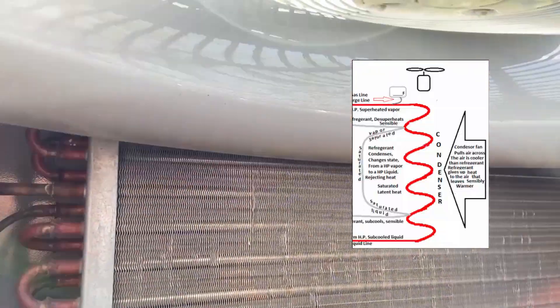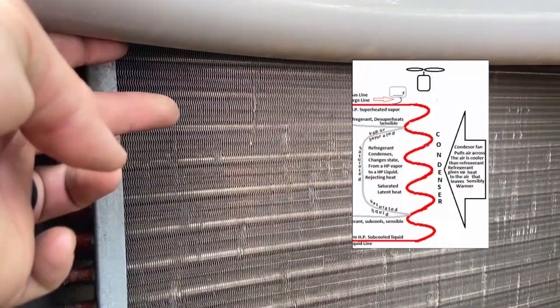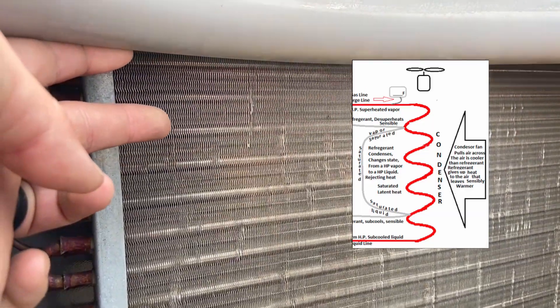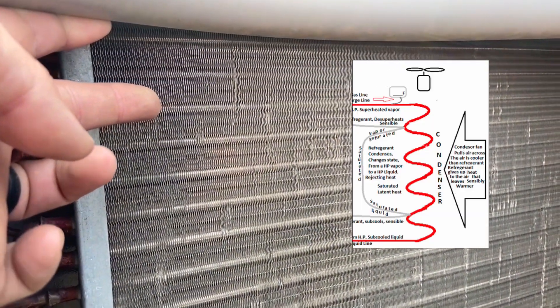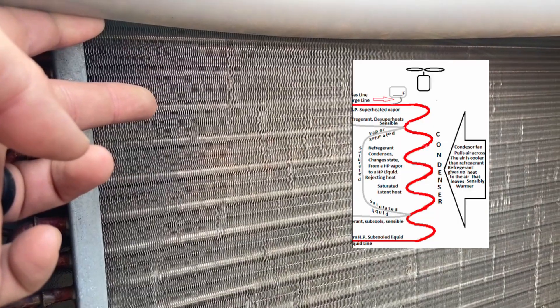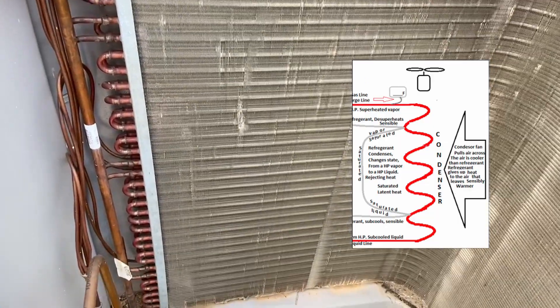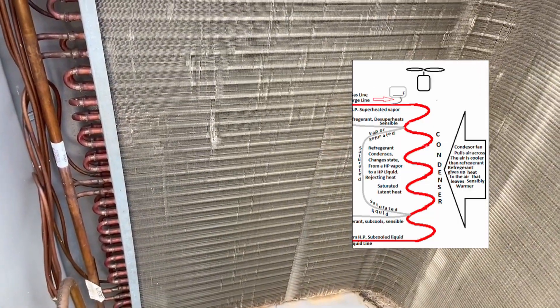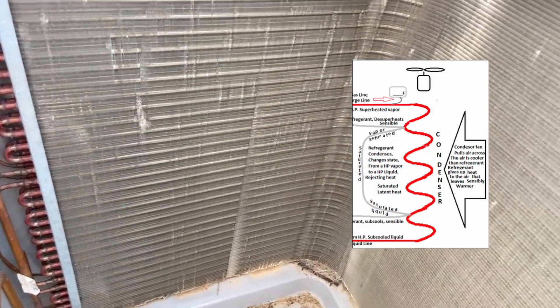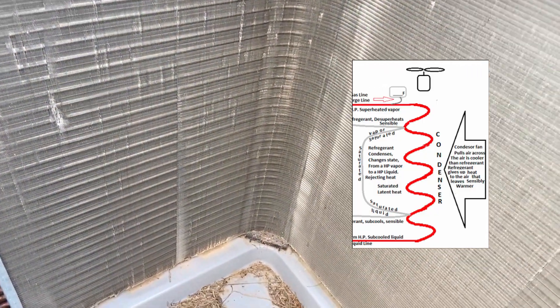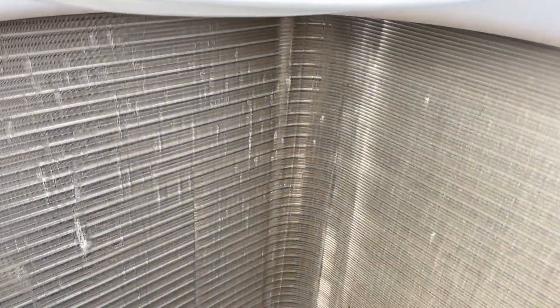Approximately the very top section of this condensing coil is where the refrigerant de-superheats — that's sensible heat, it's simply dropping in temperature. The middle section of this condensing coil is where condensing occurs: the refrigerant is literally changing state from a vapor back into a liquid. As it changes state, it's rejecting a massive amount of latent heat.